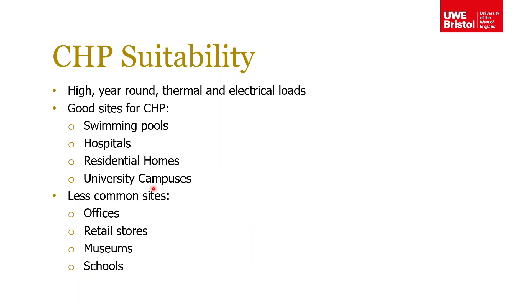Good sites also include residential homes and university campuses. Sites that aren't well-suited for CHP are offices, retail stores, museums, and schools — anywhere that doesn't have a consistently high year-round demand. Schools, for example, are shut during the summer, and other places switch on and off, so they don't have the high year-round thermal and electrical load that CHP really requires.